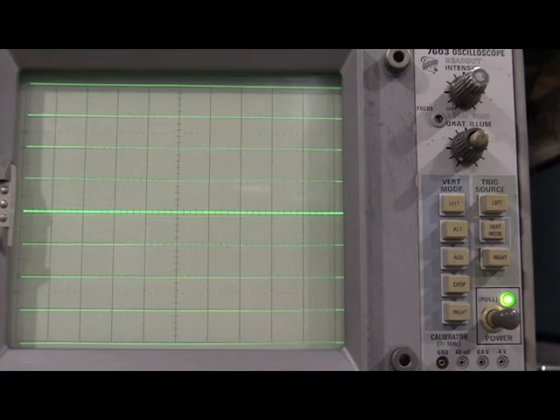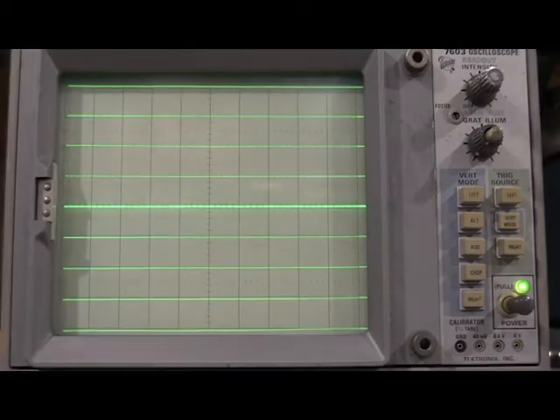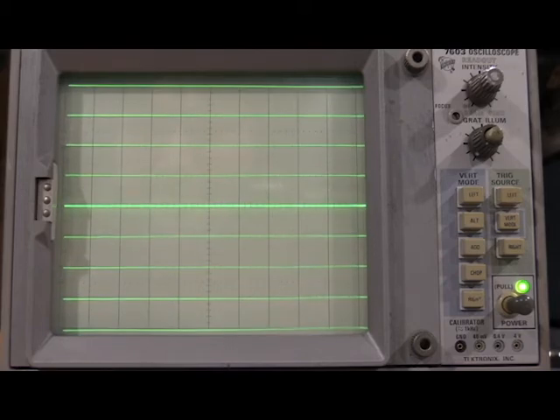Now I need to check the vertical gain in the right-hand slot. So I need to move the camera. And there's the vertical gain of the right-hand compartment. Spec is same deflection within plus or minus 1% from the 2nd to the 8th traces. So you actually throw out the top and bottom because that's the 1st and the 9th. But then the 2nd to the 8th should be within 1% of the other compartment. And it does look pretty good.